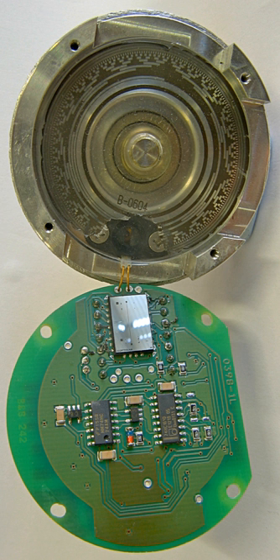An absolute encoder has multiple code rings with various binary weightings which provide a data word representing the absolute position of the encoder within one revolution. This type of encoder is often referred to as a parallel absolute encoder. A multi-turn absolute rotary encoder includes additional code wheels and gears. A high-resolution wheel measures the fractional rotation, and lower-resolution geared code wheels record the number of whole revolutions of the shaft.